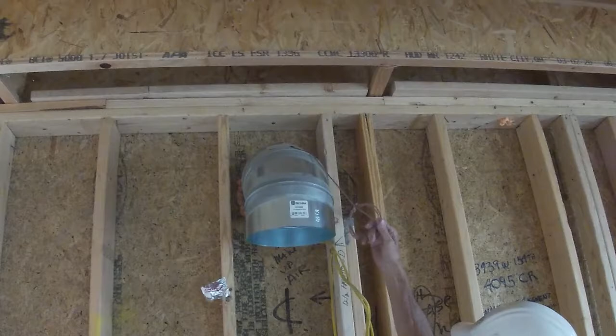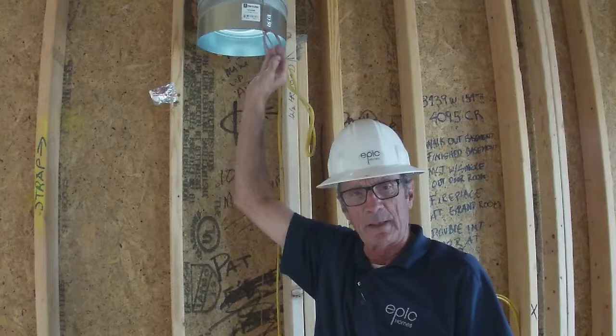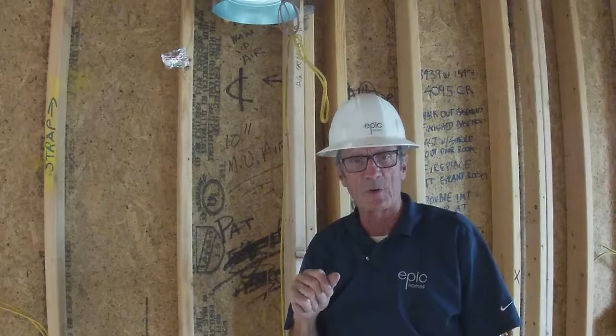This is the hood for the gas cooktop. And hood power, there's a little brown wire here. This is the low volt for makeup air. The range that you've selected, you've asked for additional CFM capability, and there's an electronic damper downstairs. When the heat gets to a certain BTU, that electronic damper will kick on and it'll draw room air from the great room area, so you're not just sucking air completely out of the living space. We're adding additional outside air when that CFM requirement arises.